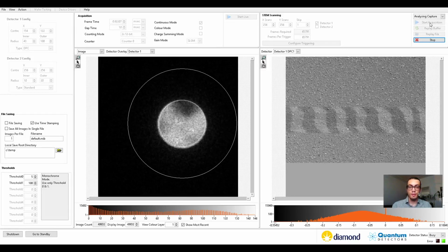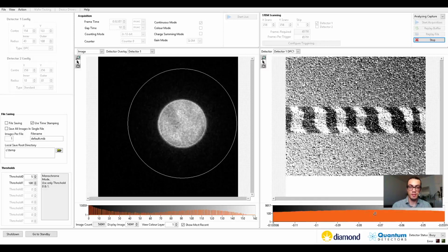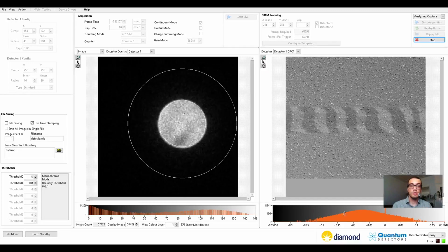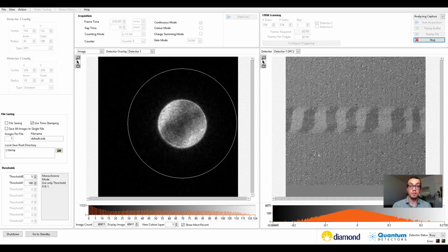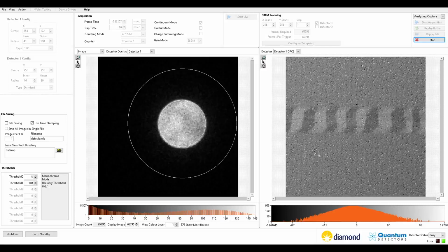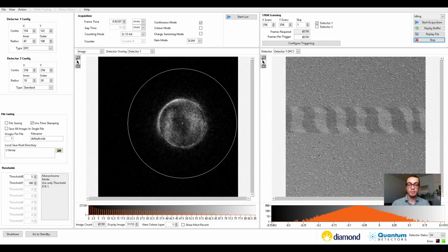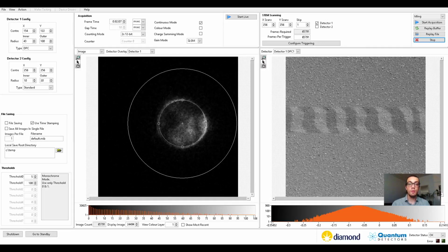The histogram bar below both of the windows allows us to select a specific contrast at the moment when it's imaged. Double-clicking on the histogram will reset the contrast to minimum and maximum values present in the data. So far, we have only looked at a single DPC component, but the view can be changed to the second orthogonal component in the window options at the top. Once the data acquisition is finished, we can view different positions by clicking in the reconstruction window. The diffraction pattern corresponding to the particular pixel we've clicked on will be displayed on the left side.